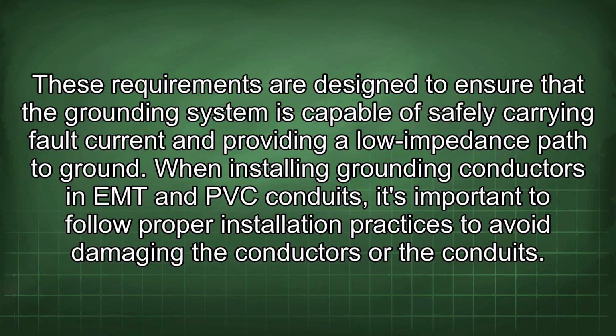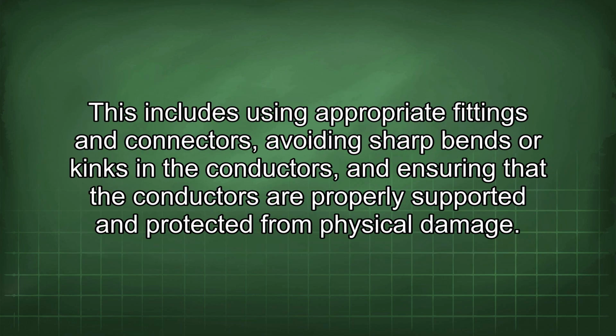When installing grounding conductors in EMT and PVC conduits, it's important to follow proper installation practices to avoid damaging the conductors or the conduits. This includes using appropriate fittings and connectors, avoiding sharp bends or kinks in the conductors, and ensuring that the conductors are properly supported and protected from physical damage.